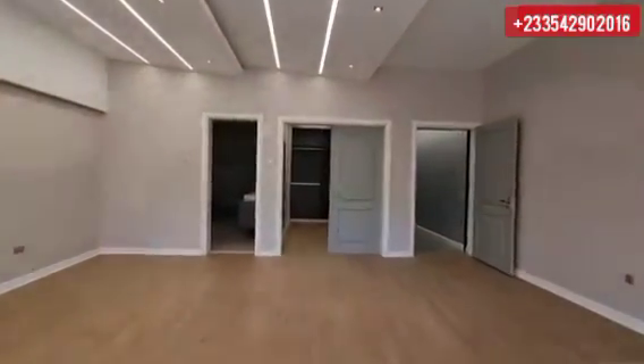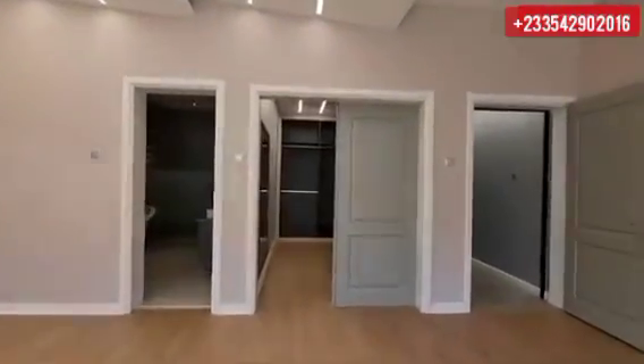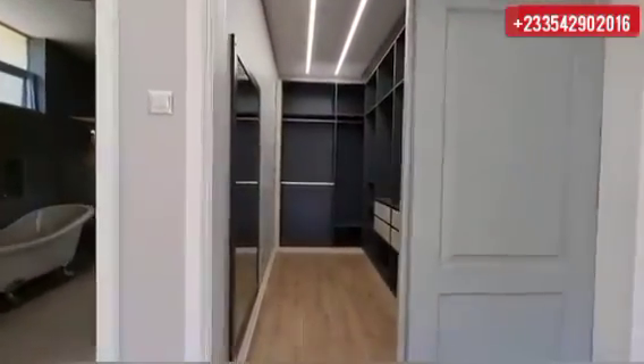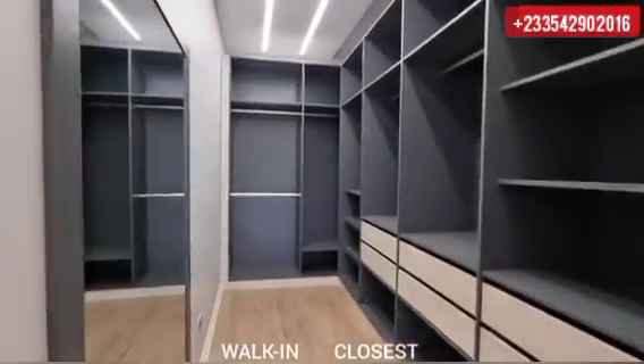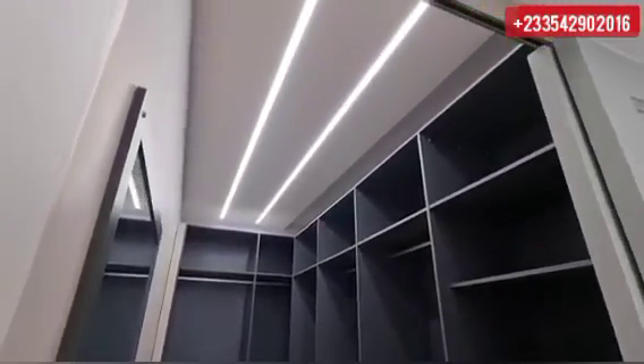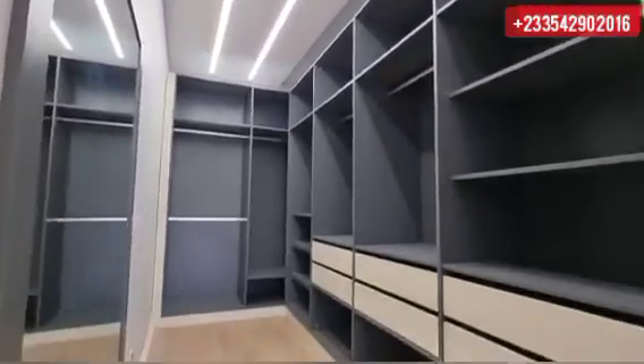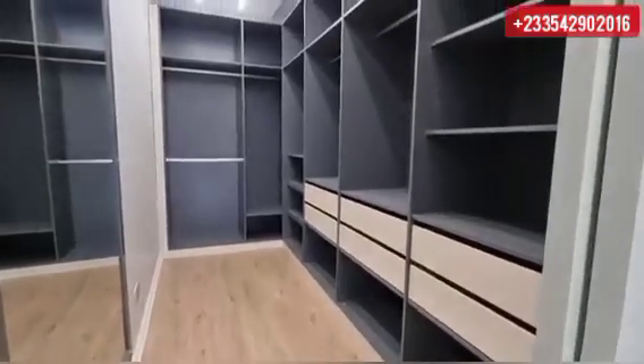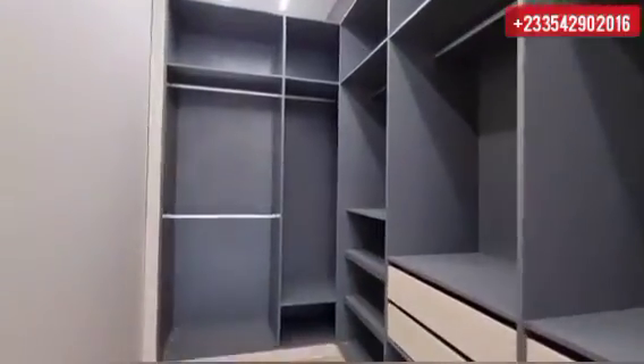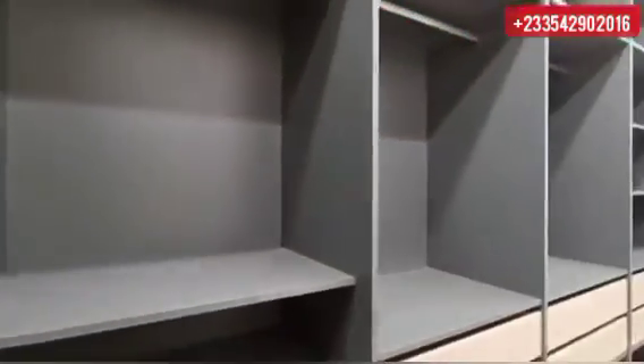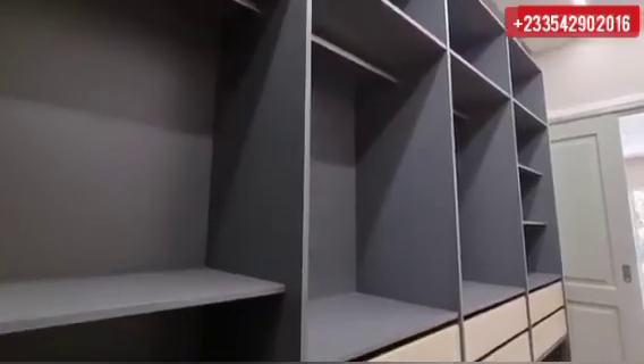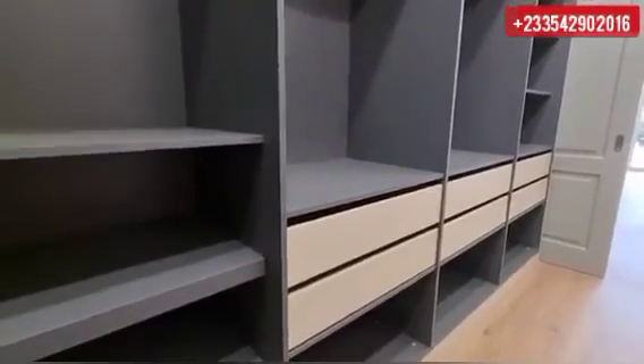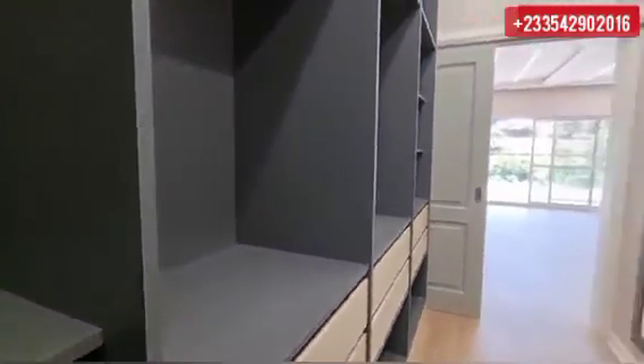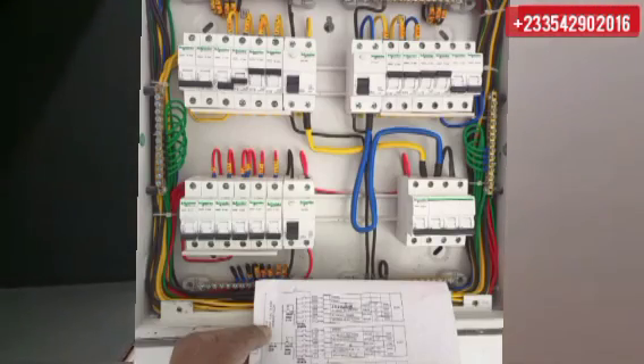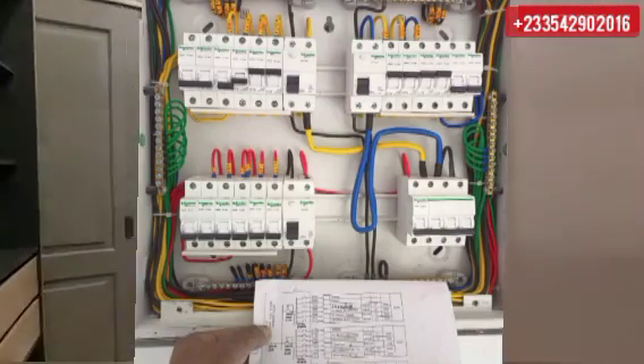Also, if you have an electric heater of about 3,000 watts, you need to divide the 3,000 watts by the voltage you have in Ghana. Some places have 110 volts, so depending on the wattage, you divide it by the voltage and then choose the appropriate breaker, the best one for that.